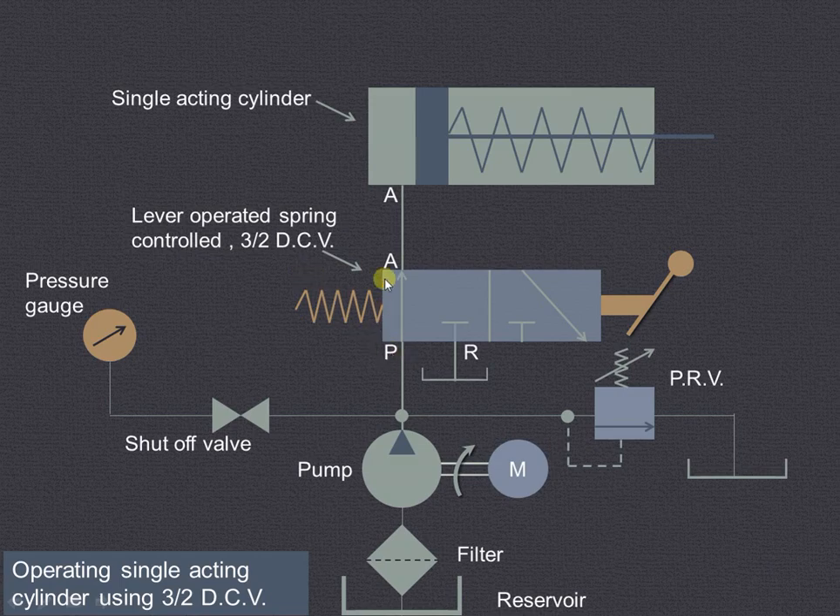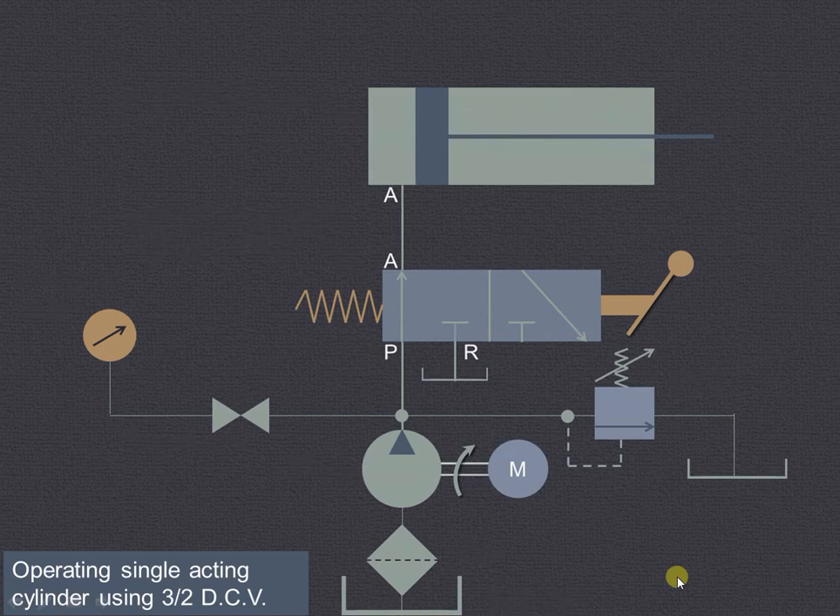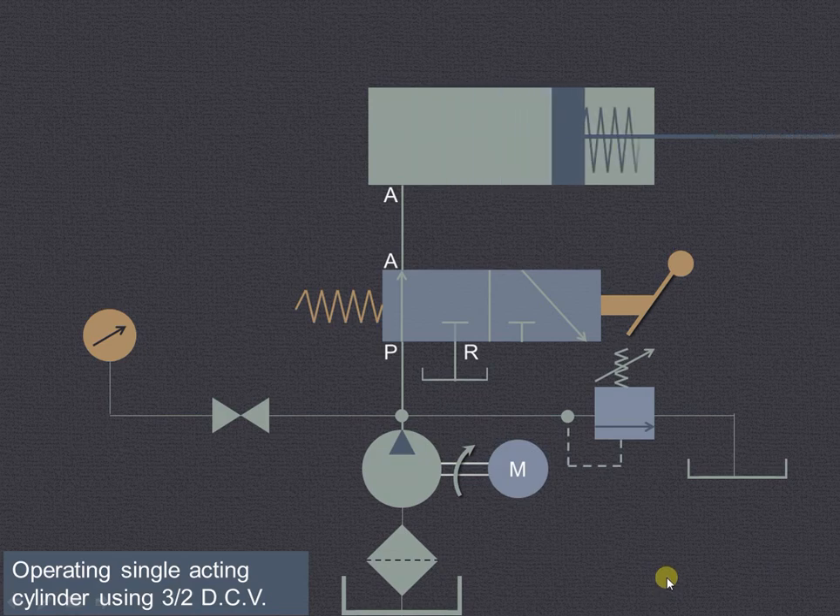There are three ways — P, A, and R — and there are two positions. This is the left position and this is the right position. For the left envelope mode, the fluid will be entering from the reservoir through the filter, pump, then pump port P to A, and from A it will cause the piston to extend, compressing the spring.